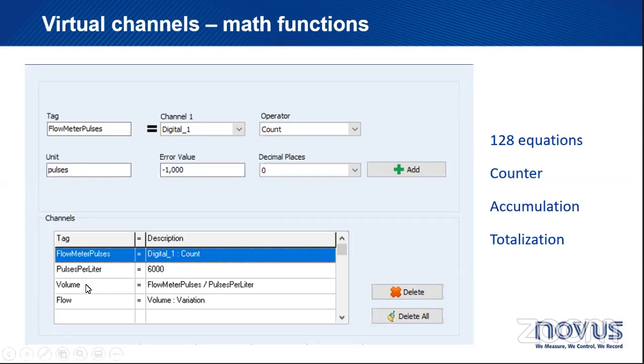So next step, I take this counter and I divide by the pulses per liter constant. And what I have is the volume in liters. So I have counted 12,000 pulses. Now I divide it by 6,000. What do I have? 2 liters, and so on. I can also find out what my flow is.